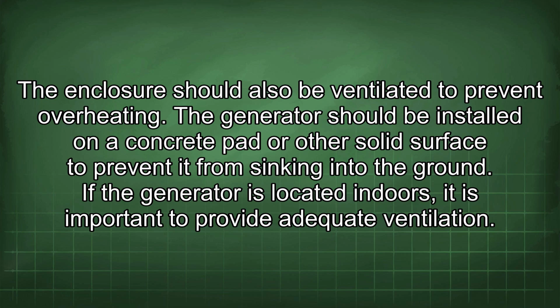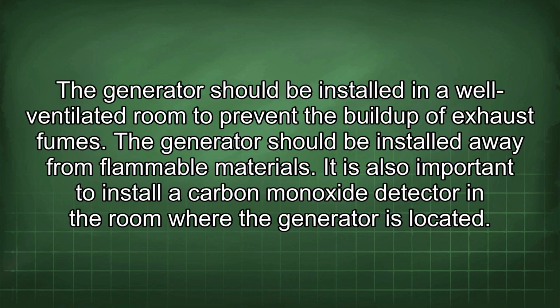ground. If the generator is located indoors, it is important to provide adequate ventilation. The generator should be installed in a well-ventilated room to prevent the buildup of exhaust fumes. The generator should be installed away from flammable materials. It is also important to install a carbon monoxide detector in the room where the generator is located.